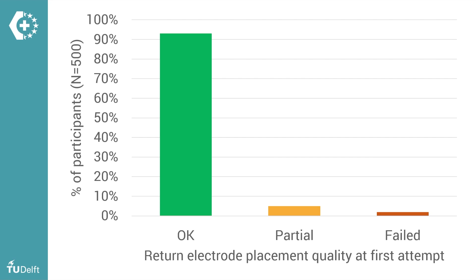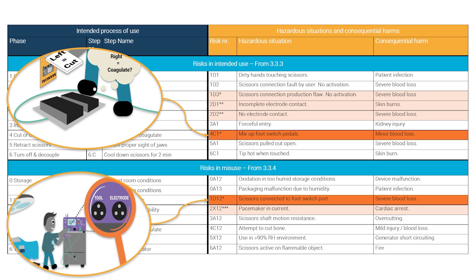In the same experiment, you could test these two situations in which the user mixed up the controls for cut and coagulate, or connected the scissors to the wrong port on the generator. These also are use errors of which the occurrence probability can be estimated by simulating the use of the device.